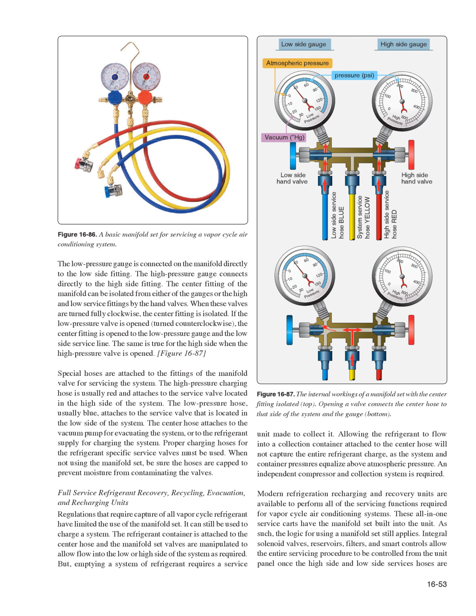But emptying a system of refrigerant requires a service unit made to collect it. Allowing the refrigerant to flow into a collection container attached to the center hose will not capture the entire refrigerant charge, as the system and container pressures equalize above atmospheric pressure. An independent compressor and collection system is required.